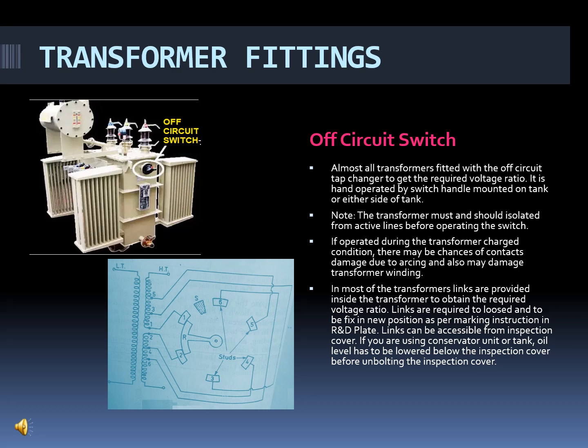If we are using a conservator tank, that means an oil tank, then the oil level has to be lowered below the inspection cover before unbolting it, because the inspection cover has oil behind it. You have to lower the oil level below the inspection cover, and only then can the inspection cover be opened safely and you can access the links.